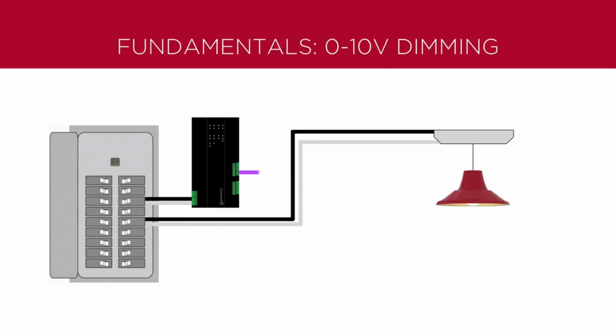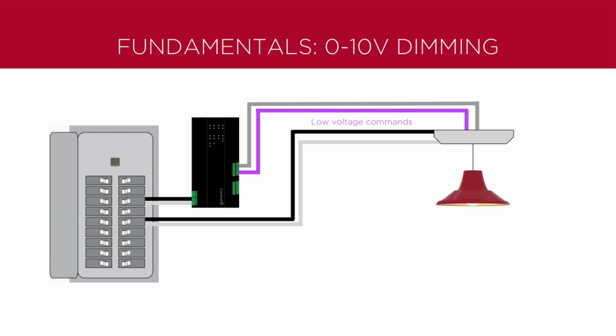Fundamentals for 0 to 10 volt dimming. 0 to 10 volt dimming is commonly used for fixtures using fluorescent ballasts and can also be used with fixtures using LED drivers. It uses an analog, low-voltage control. The ballast or driver interprets the commands and performs the actual dimming of the load. When installing 0 to 10 volt dimming, the sink is the ballast or the driver in the fixture, and the source is the control device.